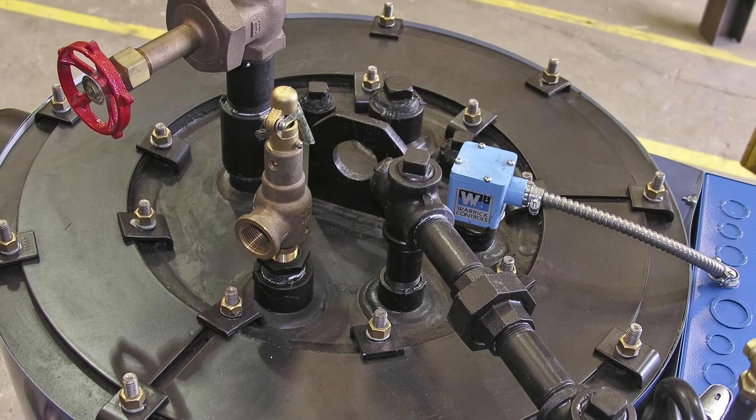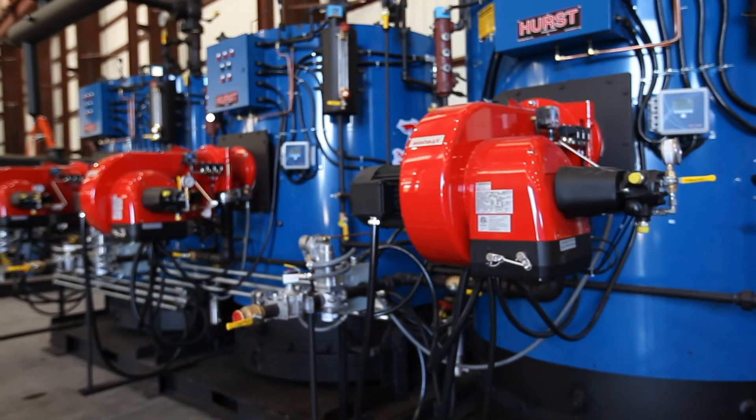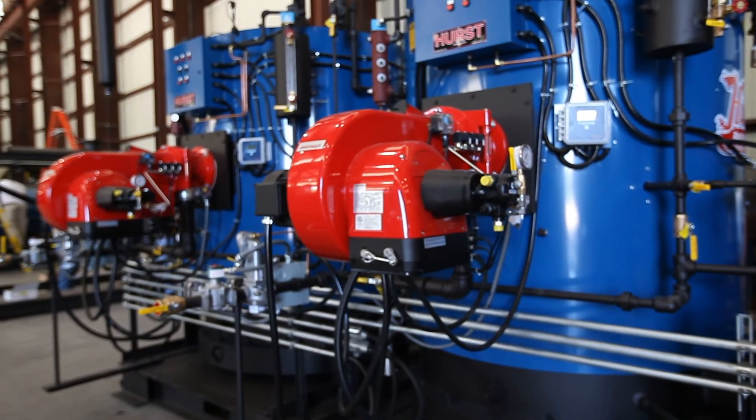A lot of boilers, you have to work on the top of the boiler because the burner's up on top, or you have to lay on the ground. Our boiler is a center-mounted fire tube boiler. You see the burner in the background. The fire fires into the tube, into the pipe, in a cyclonic type development, which causes a lot of turbulence. That gives you heat release, and when you get this heat release, it affects efficiency. Then from there, that cyclonic turn goes down and leaves through the windows of the boiler or the ports into the three other passes available in the boiler. So you have a total of four paths. It goes out and goes through those passes, scrubbing along through those fins. Then it goes out through the stack, where you get a much lower stack temperature.